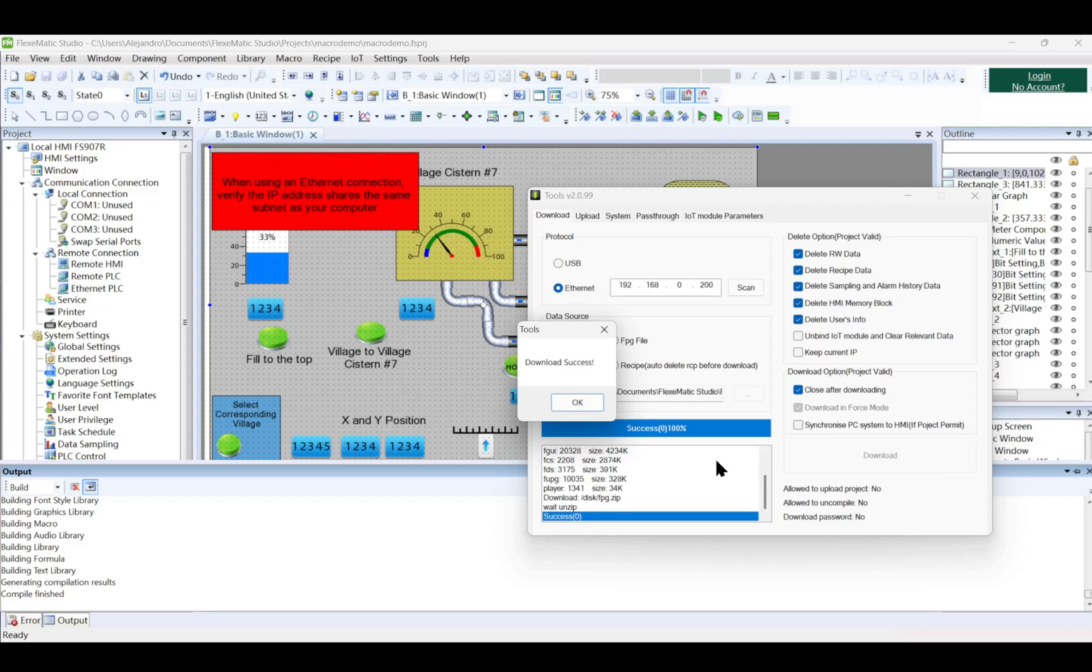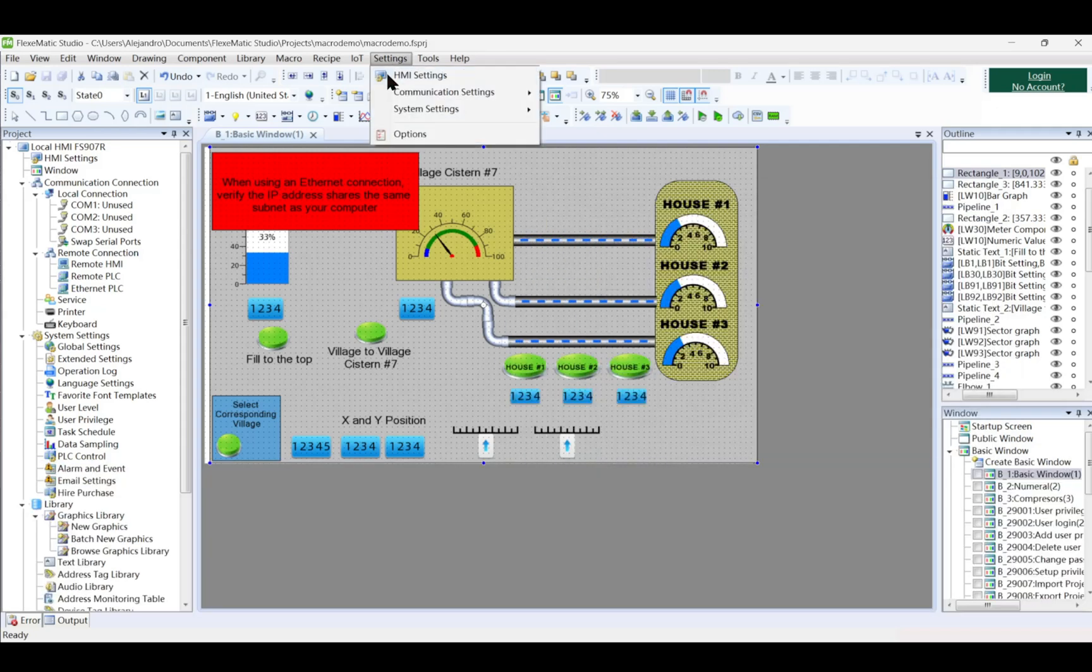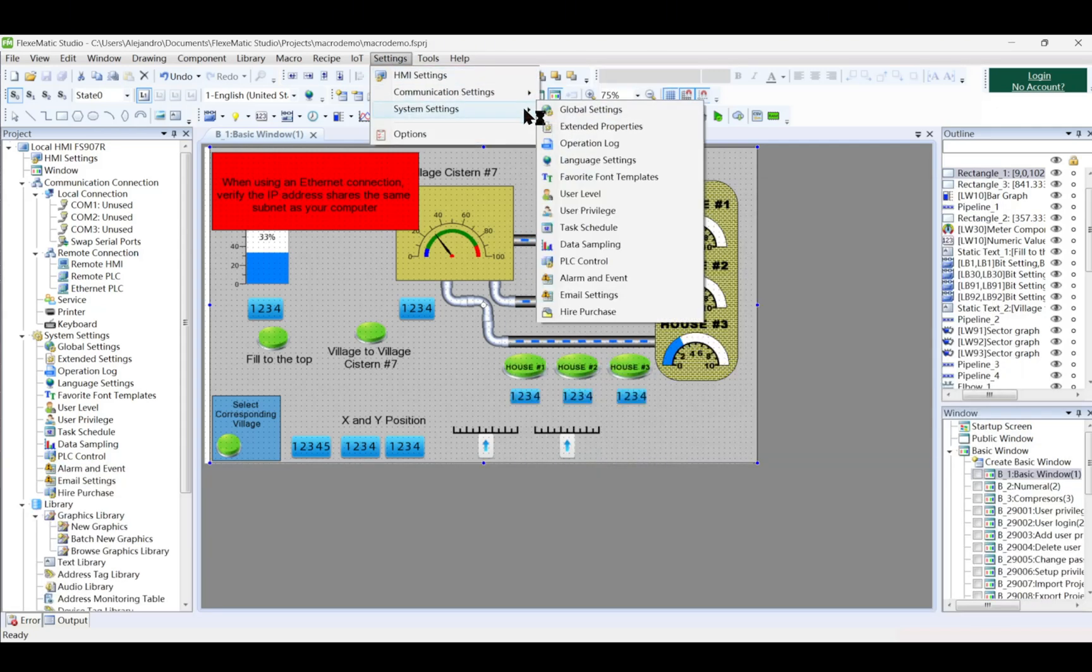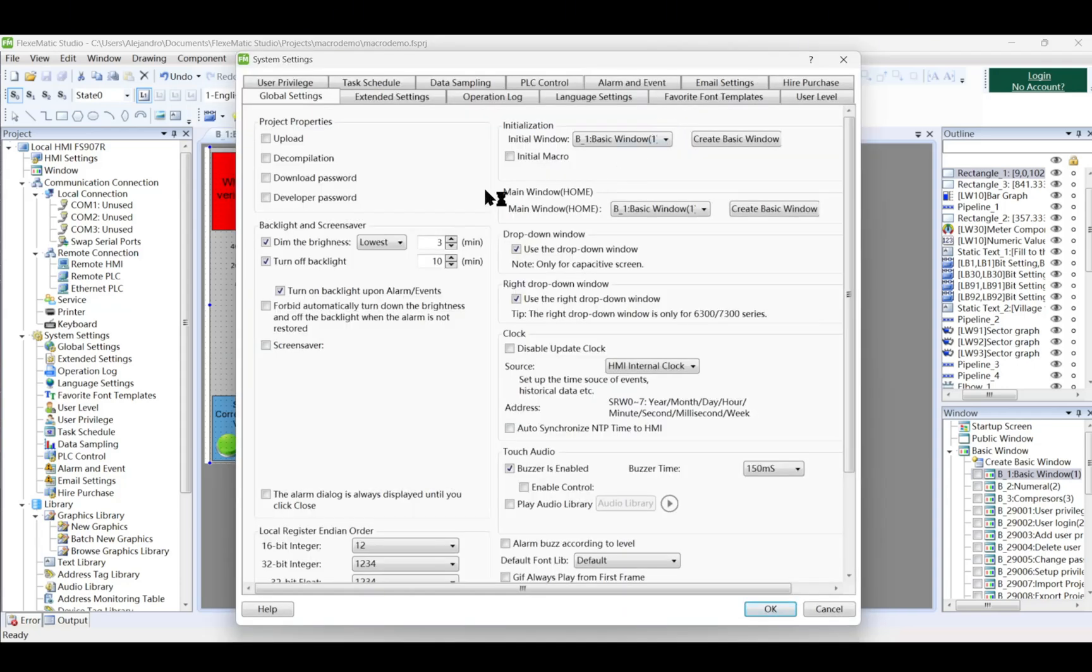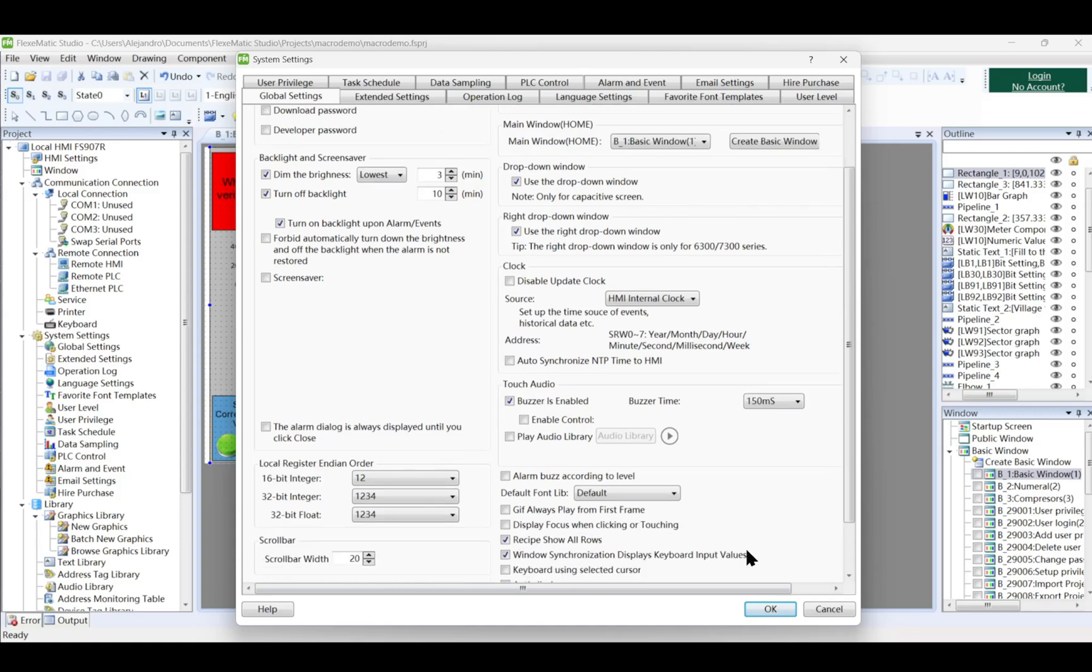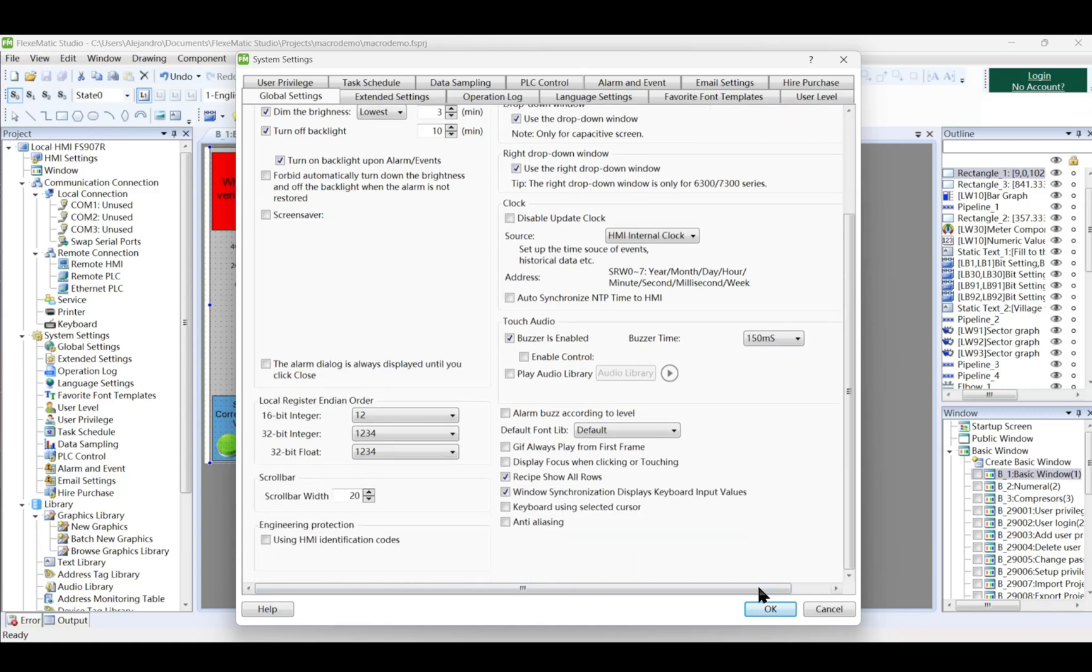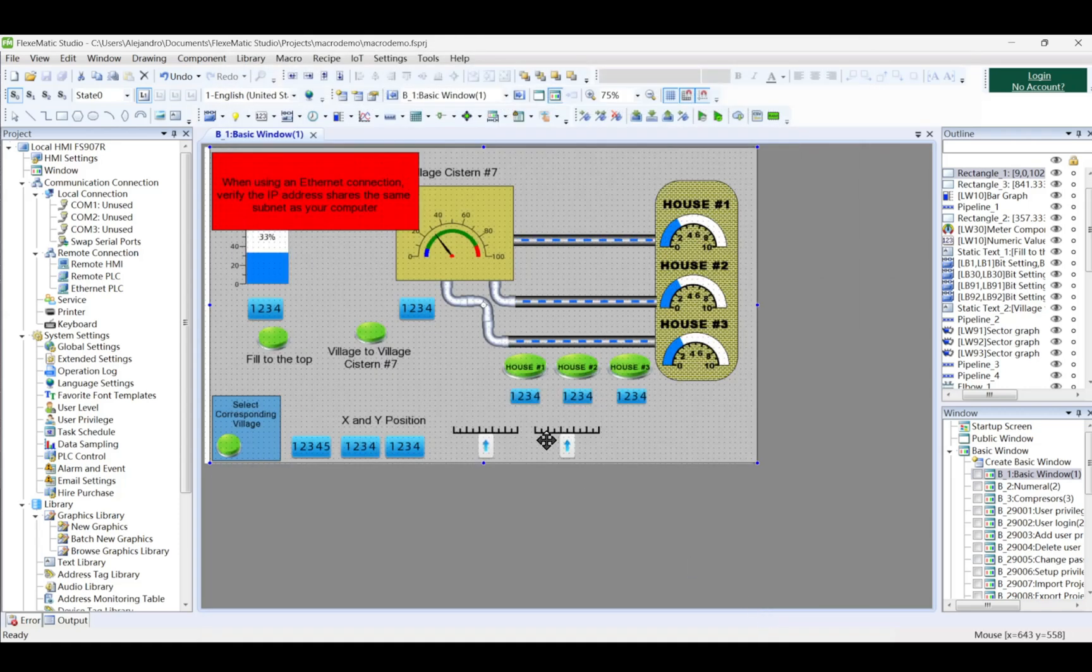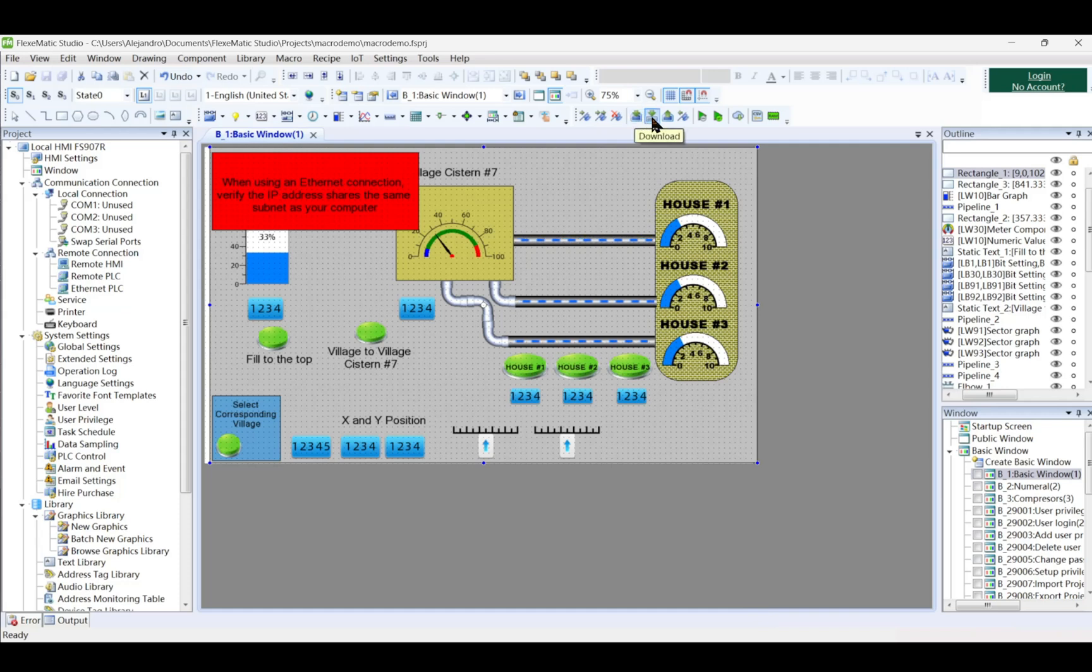To perform an upload operation, configure the project properties in global settings to allow uploads and set an upload password. Enabling project uploads from the HMI to FMS requires an 8-digit decimal upload password, with the default being 88888888. Download the project again so that the upload function can be enabled.